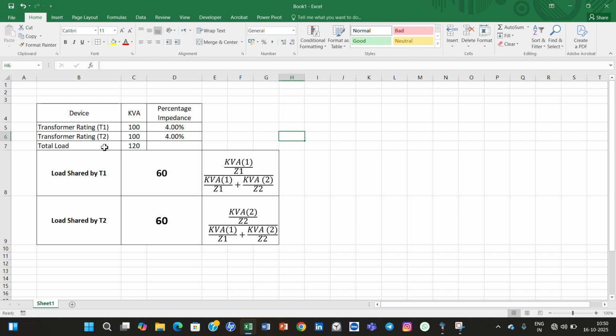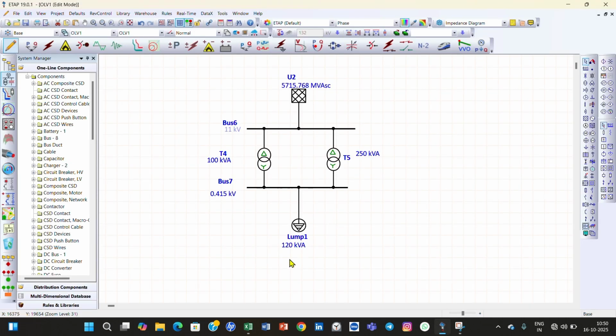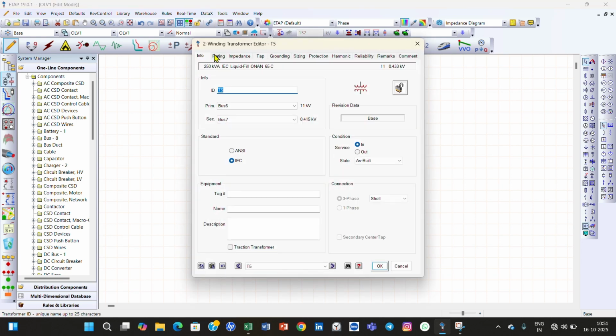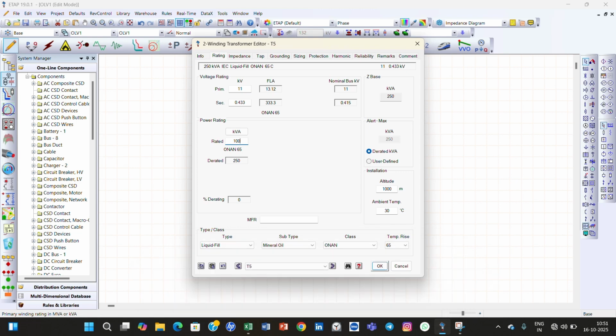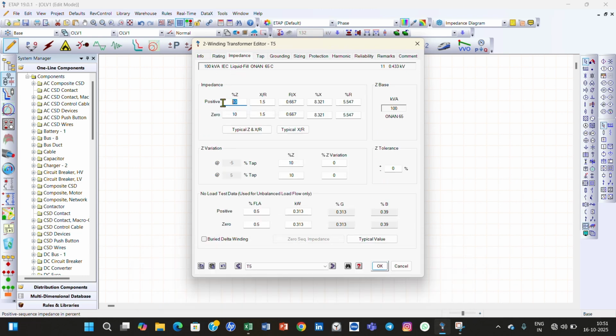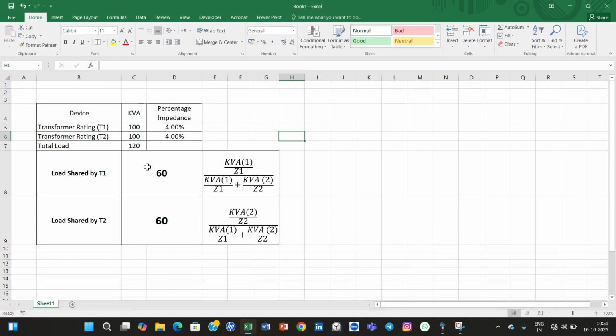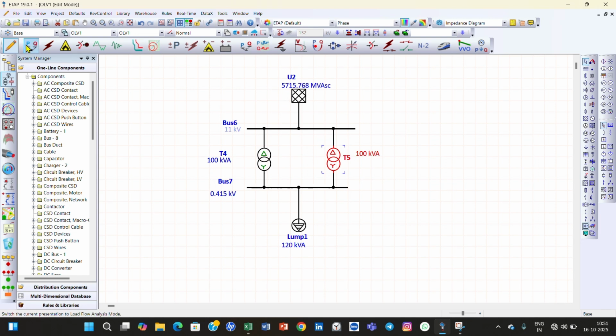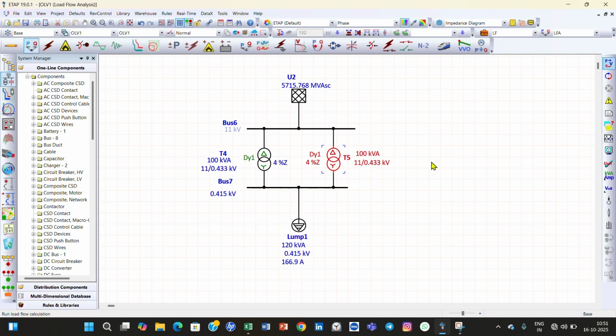Total load is 120 kVA. So the first transformer is 100 kVA, and we will set the second transformer rating as 100 kVA and percentage impedance 4%, 4%. Click OK. We have kept a similar configuration here: the transformer is 100 kVA, percentage impedance is 4%, and total load is 120 kVA. Now we will check the ETAP results and see how the load is shared. You can see transformer one shares 60 kVA and transformer two shares 60 kVA.